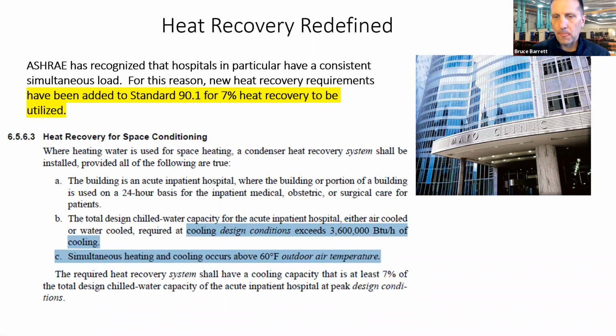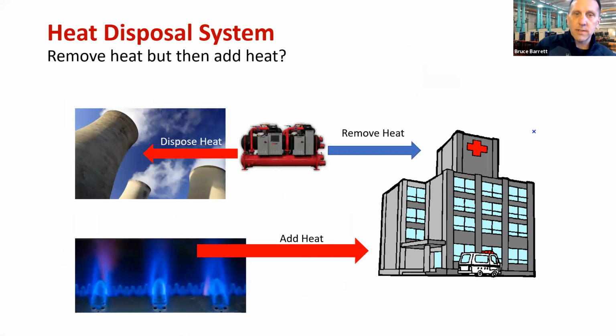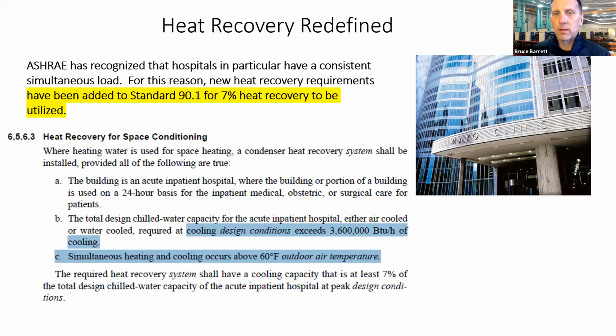Now this is a biggie. This is frankly changes in building code. The new 90.1 standard does have it written in that 7% of the available simultaneous heat must be recovered on buildings that have beds, hospital beds, 300 tons and greater. So if you do the math, that's a great application for a 300-ton job to have a very small heat recovery system and comply with that standard of 90.1.